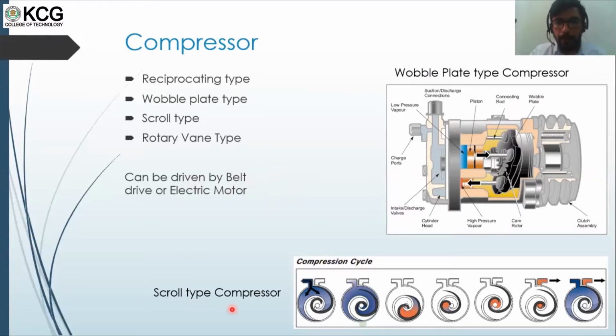The scroll type compressor, here I have shown the working. So when the scroll is at the inlet position, your refrigerant will be sucked in, and slowly as the vane rotates, it will get trapped in the vane and it will get compressed. Once it reaches the center, it will be delivered, and again the cycle repeats. So the scroll type compressor is very less seen, or I would say the most used is the wobble plate type compressor, as it is simple in construction and also the life is longer.